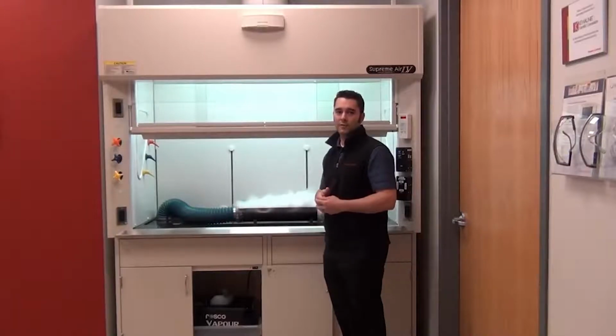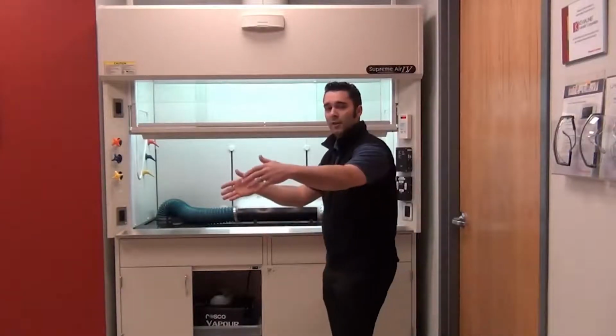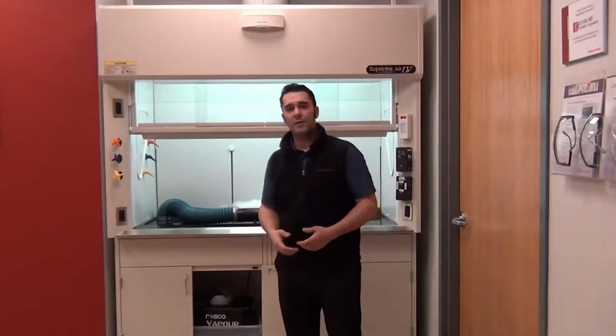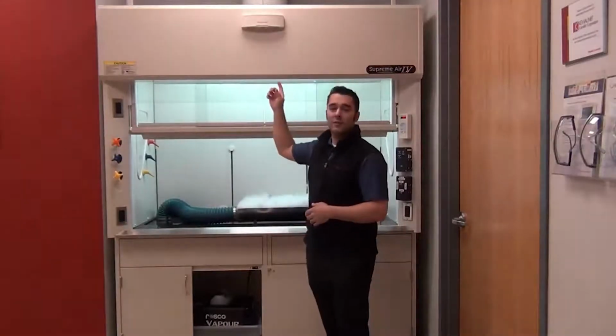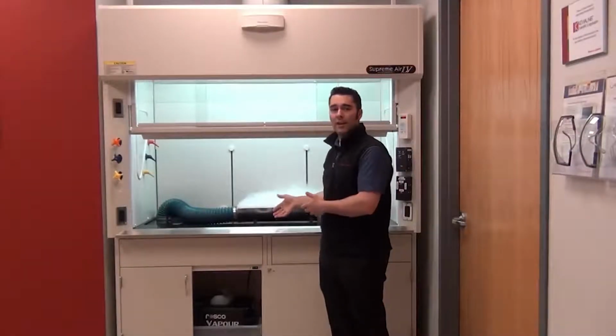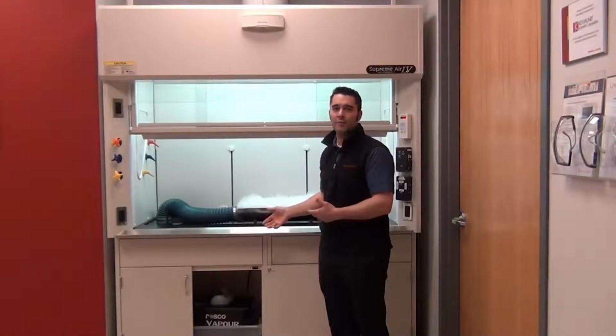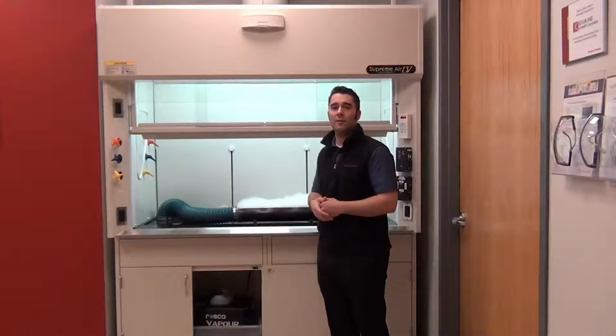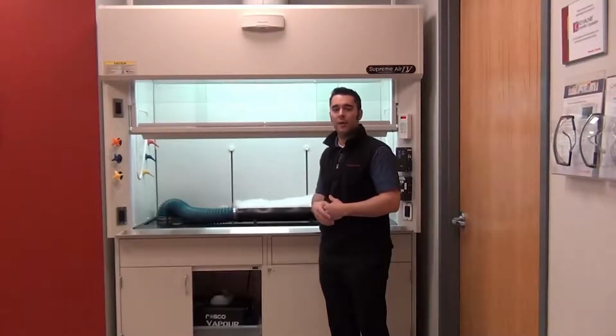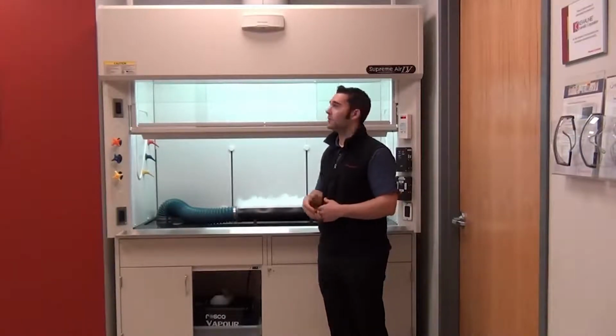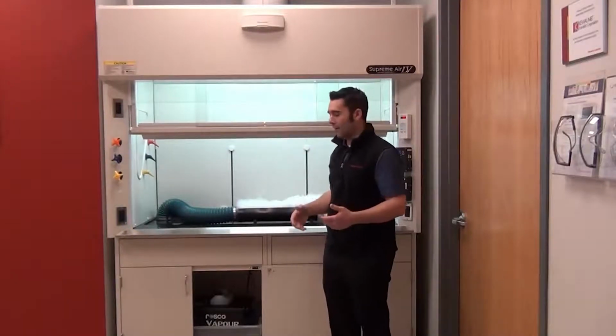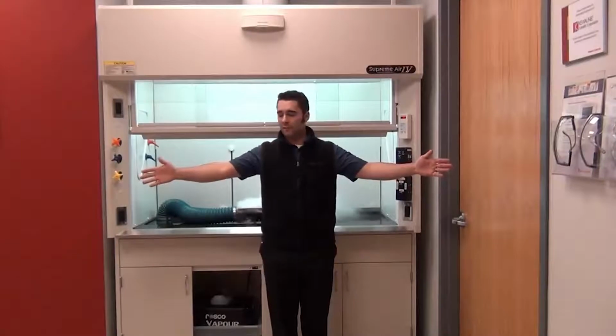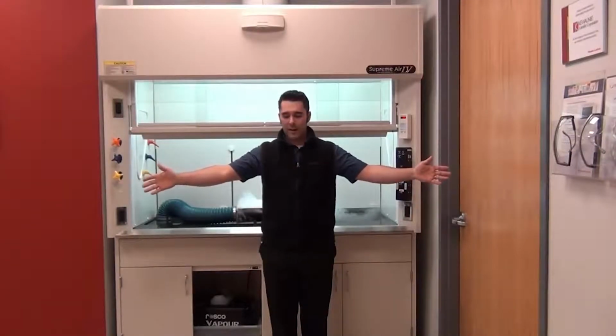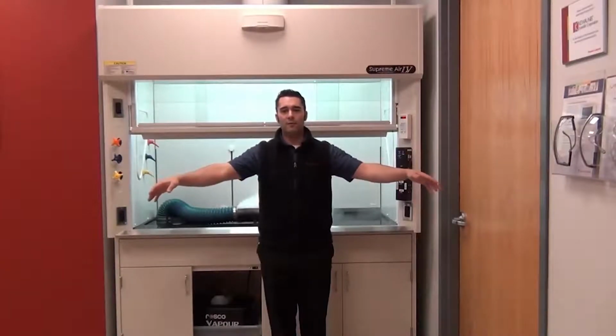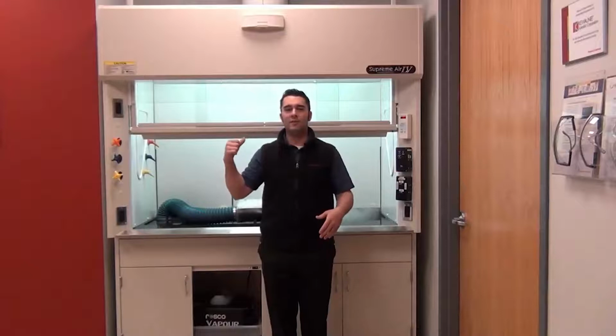setback as a nuisance. So take for instance if I had a workbench sitting right in front of this fume hood 3 or 4 feet away, when a person is sitting in front of a chair and rolling back and forth, this thing is going to pick up their motion. Now that person is not working inside of the fume hood, so that fume hood does not have to run at 100% of its max capacity. It can actually drop down to a 40% reduction in its energy, giving it 60 feet per minute instead of 100 in this particular application, which will net you 40% energy savings just by putting this device on the fume hood. Again, if I had a wide range of motion Doppler sensor that was looking at a 120 degree angle of view, what's going to happen is anything in front of that, in that 120-degree angle view, is going to get picked up as motion and trigger this thing to stay in full flow.